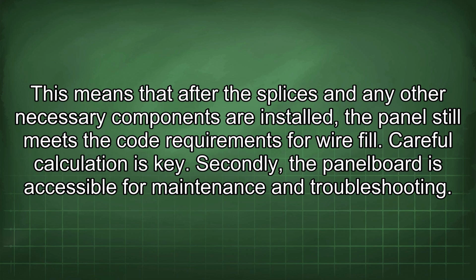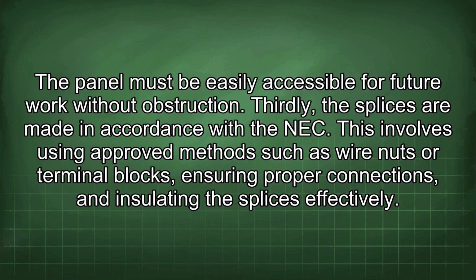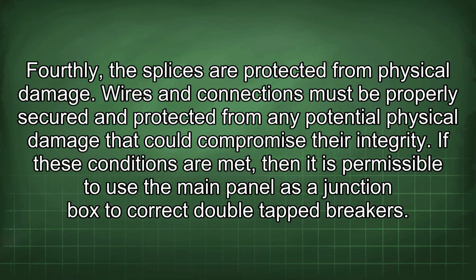Secondly, the panel board is accessible for maintenance and troubleshooting. The panel must be easily accessible for future work without obstruction. Thirdly, the splices are made in accordance with the NEC. This involves using approved methods such as wire nuts or terminal blocks, ensuring proper connections, and insulating the splices effectively. Fourthly, the splices are protected from physical damage. Wires and connections must be properly secured and protected from any potential physical damage that could compromise their integrity.